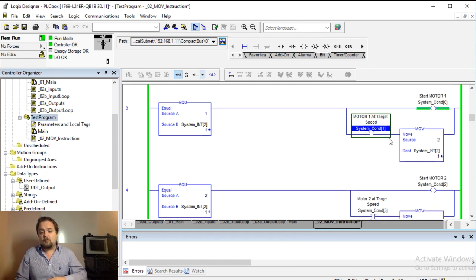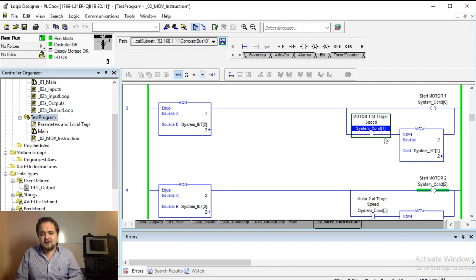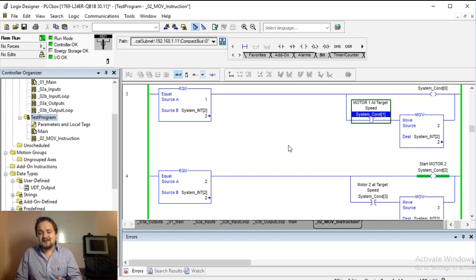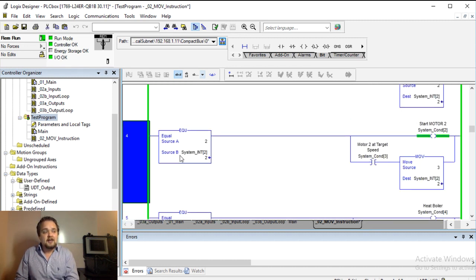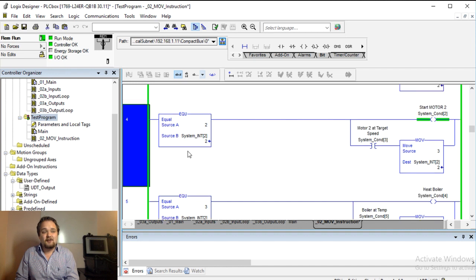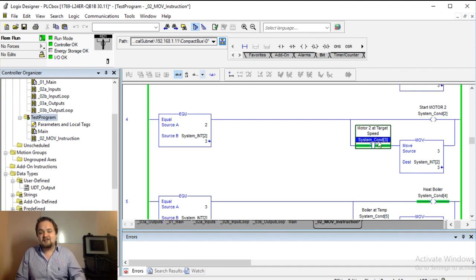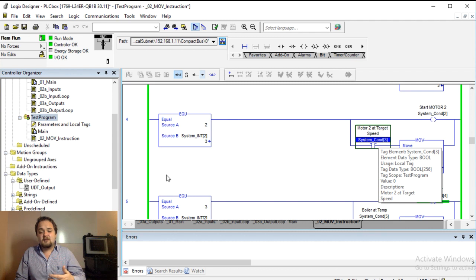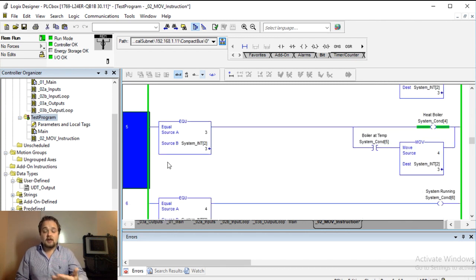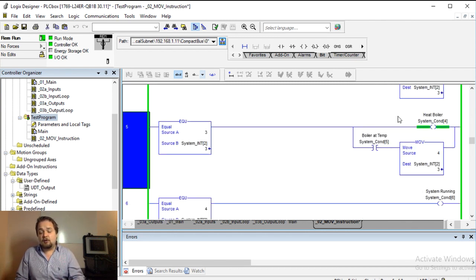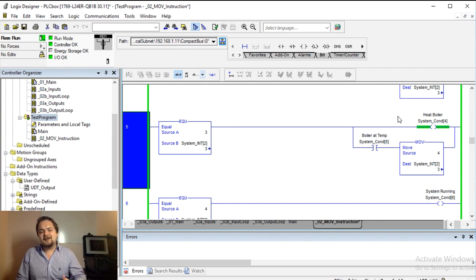But essentially here it's just waiting for that start to complete and for the motor to be at target. Once the motor is at target, I'm just manually toggling this with control T, so once the motor is at target speed you'll notice that the system has stepped to the next sequence or the next rung. In this case that rung is just looking for motor two. Very similarly once it's at target speed the system can move on to the next process. The next step is going to be heat a boiler.